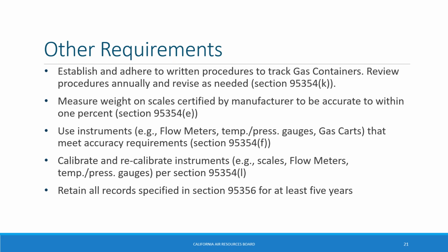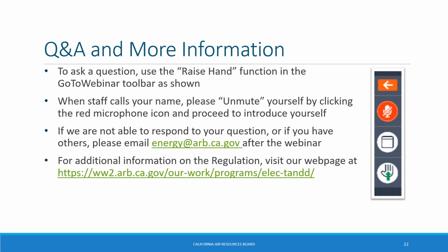Scales, flow meters, and temperature and pressure gauges must be calibrated and recalibrated at the time intervals specified in section 95354L, and these actions must be logged pursuant to section 95354L5. Finally, all records required to be retained pursuant to section 95356 must be kept for a minimum of 5 years, with the exception of those generated prior to January 1st of 2022, which are required to be retained for a minimum of 3 years, as was the case in the original regulation.